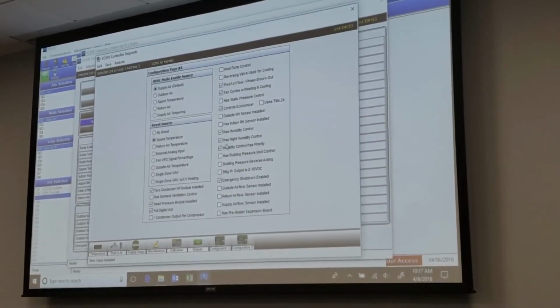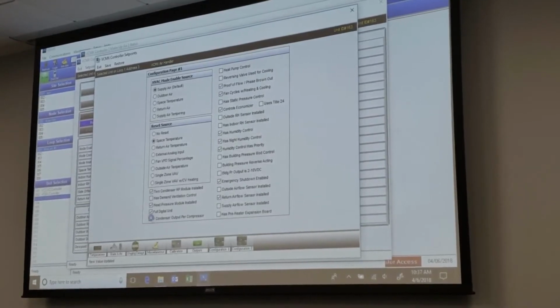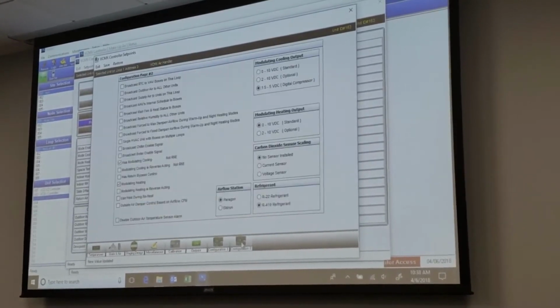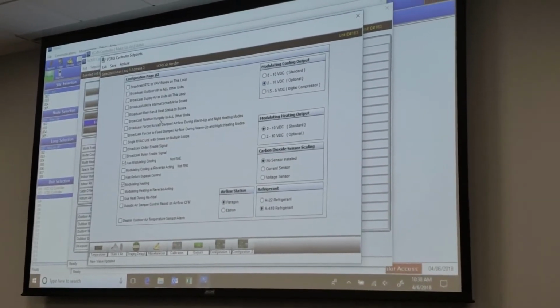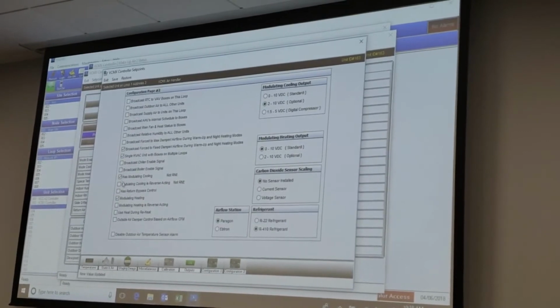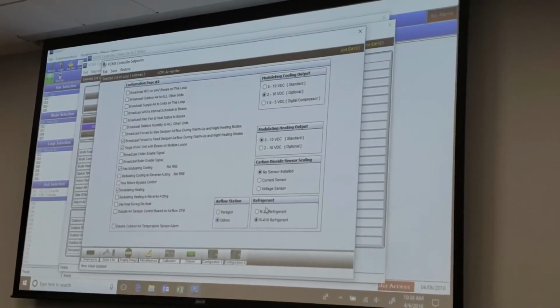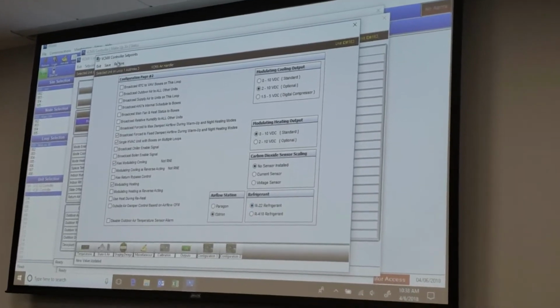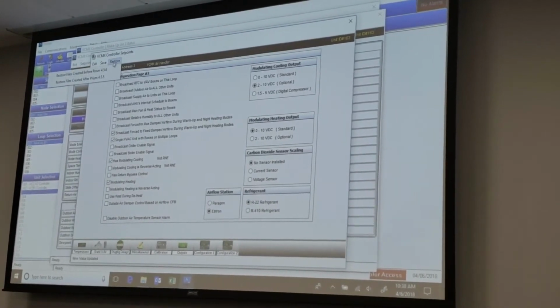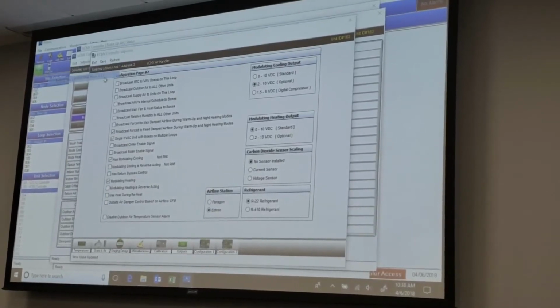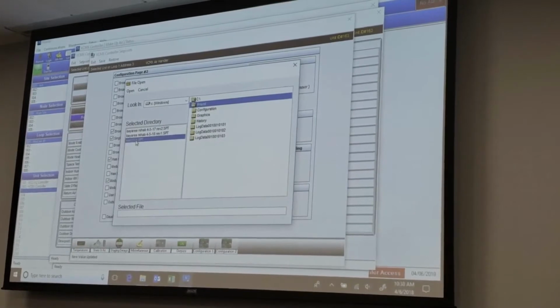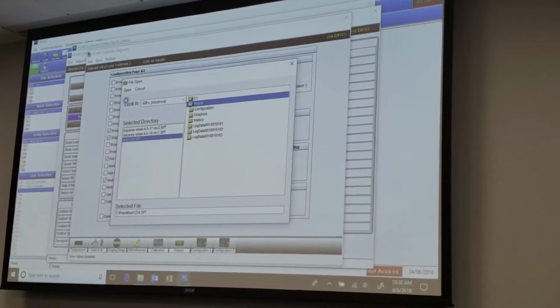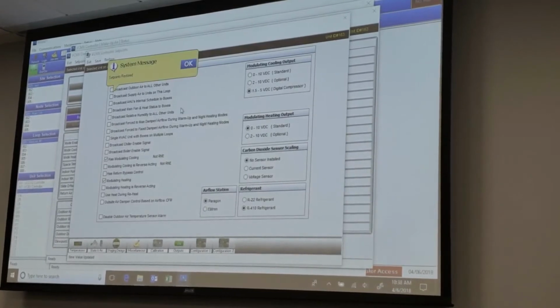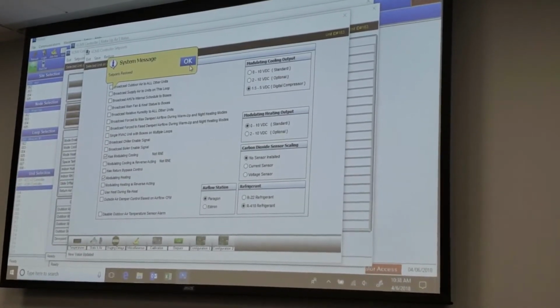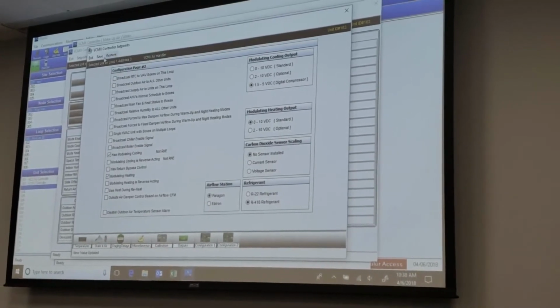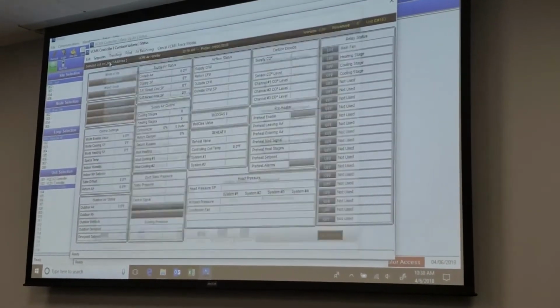I go in and start doing some crazy stuff and just trying stuff out. And then I decide, you know what, I don't like what it's doing now, or I don't know what I'm doing, so I'm going to go ahead and restore it. I can go back into this guy. This is the same set point file from when I first walked up to it, and I just hit open, and it all went back to the original set points. You can also take that guy once you save that set point file.